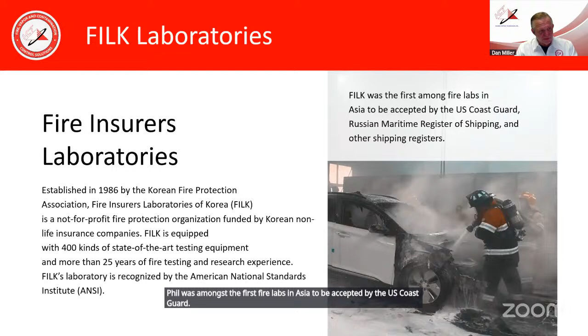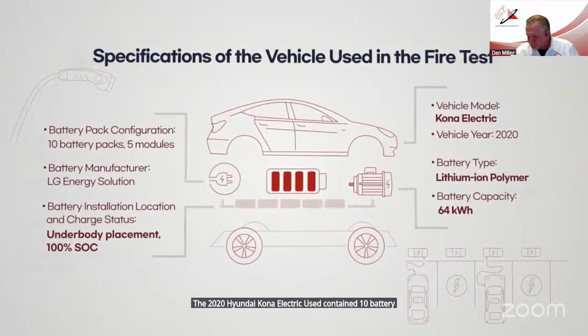On October 15th, 2024, F500 Encapsulator Agent was put to the ultimate test. The 2020 Hyundai Kona electric used contained 10 battery packs at 100% charge. Fire suppression was applied by an underbody water spraying system supplied by an outdoor hydrant. An F500 EA solution proved to absorb thermal energy 10 times faster than plain water or foam. This test took place at the KOLAS accredited Fire Insurers Laboratory of Korea.